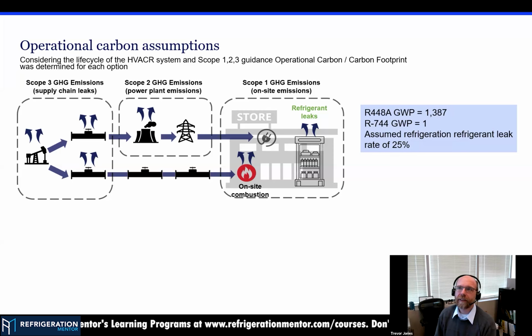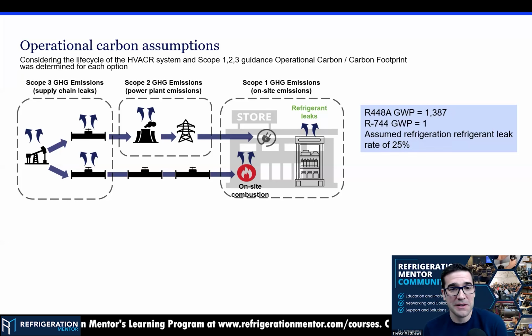And some leakage may actually be due to improper documentation of service. If you pull off 10 pounds and don't log it, you're reclaiming 10 pounds to do a service, and you put it back in, or you have to, and then you recharge, and you log that you put 10 pounds in, but you didn't, that you pulled some out first, that would look like a leak in the documentation. And you should be logging this. I was doing it 20 years ago, logging my refrigerant when I was adding. So anybody listening out there, you've got to be tracking this stuff. This is important for your customer, especially when you're doing grocery store or supermarket work. We're talking about hundreds to thousands of pounds of refrigerant. You've got to be logging that stuff. It's just part of our job as being a refrigeration professional.